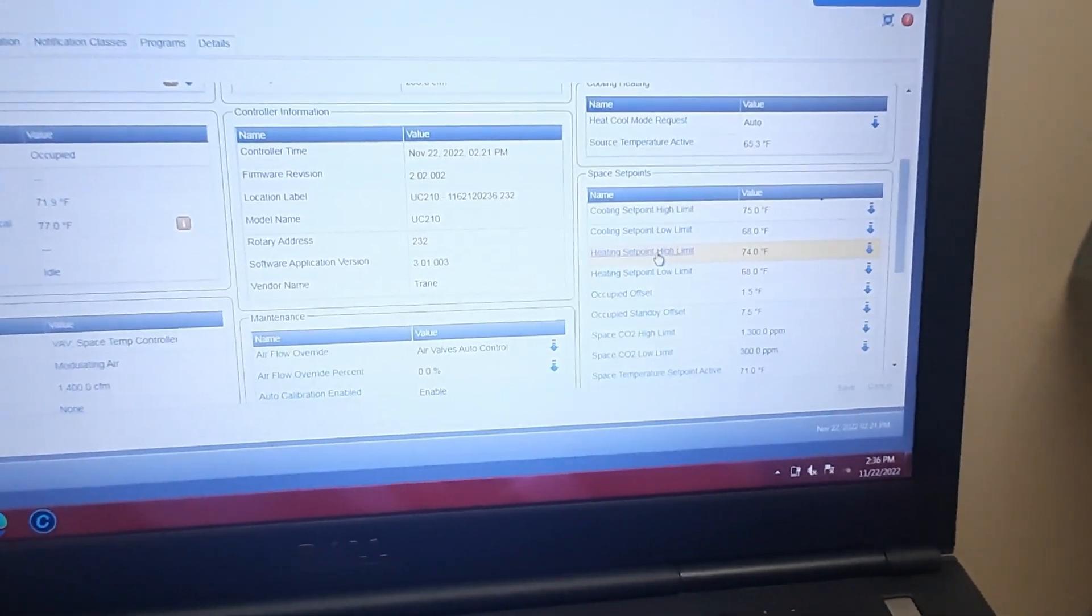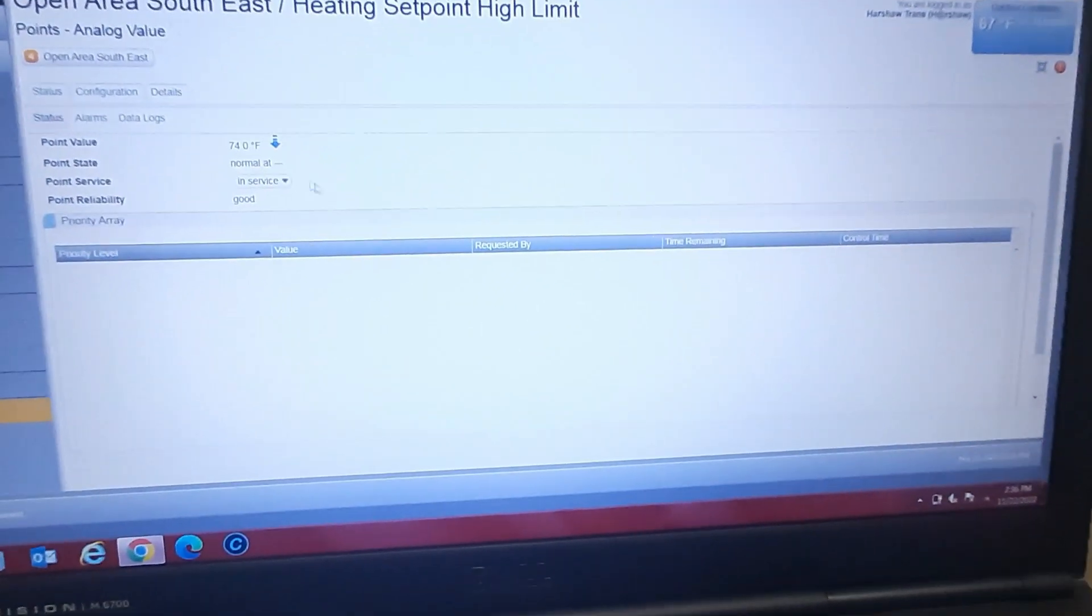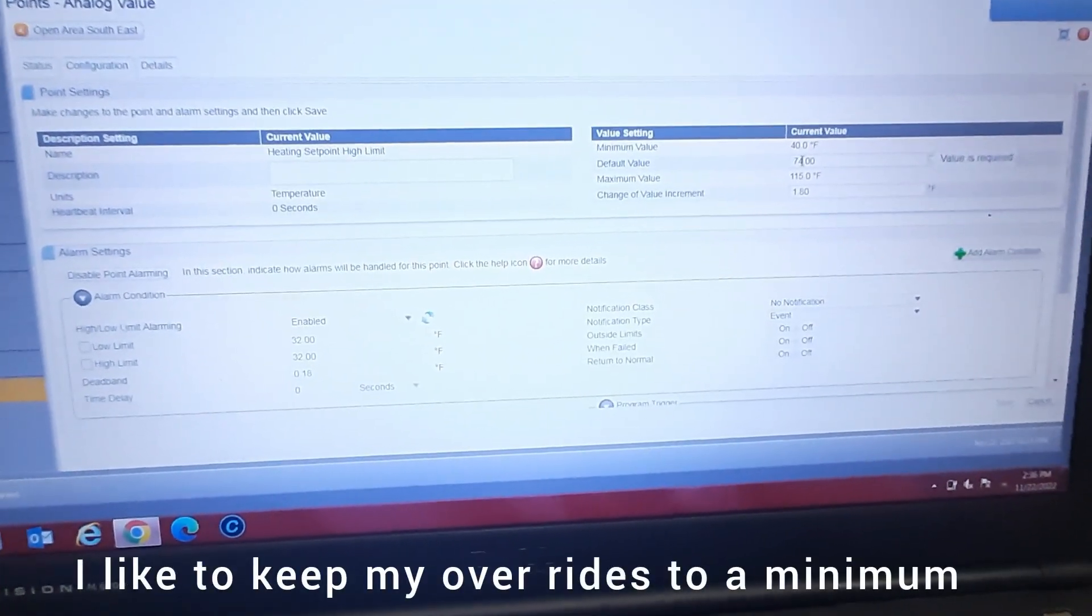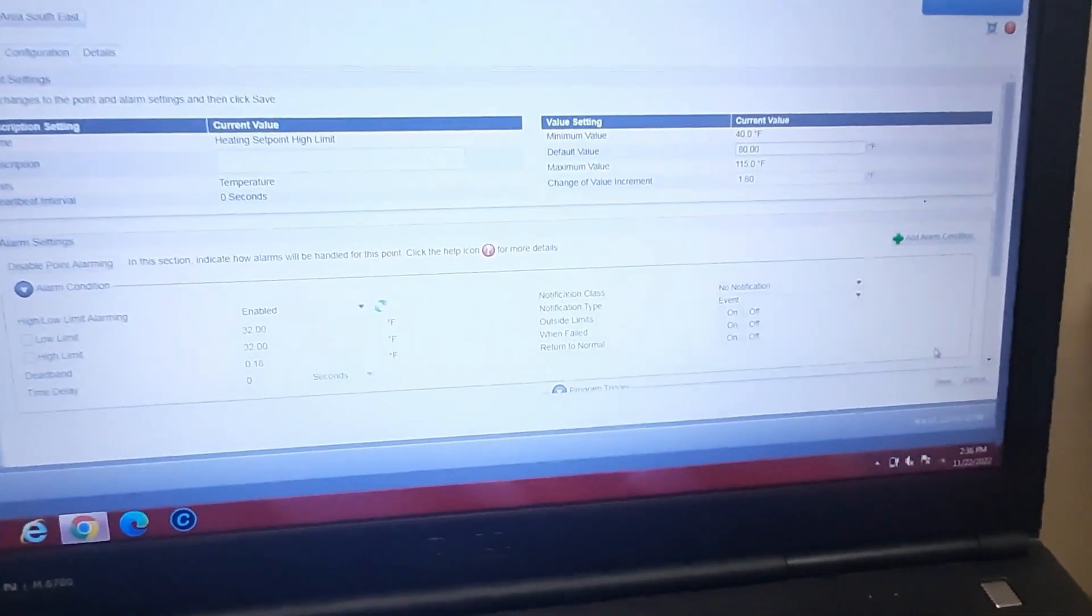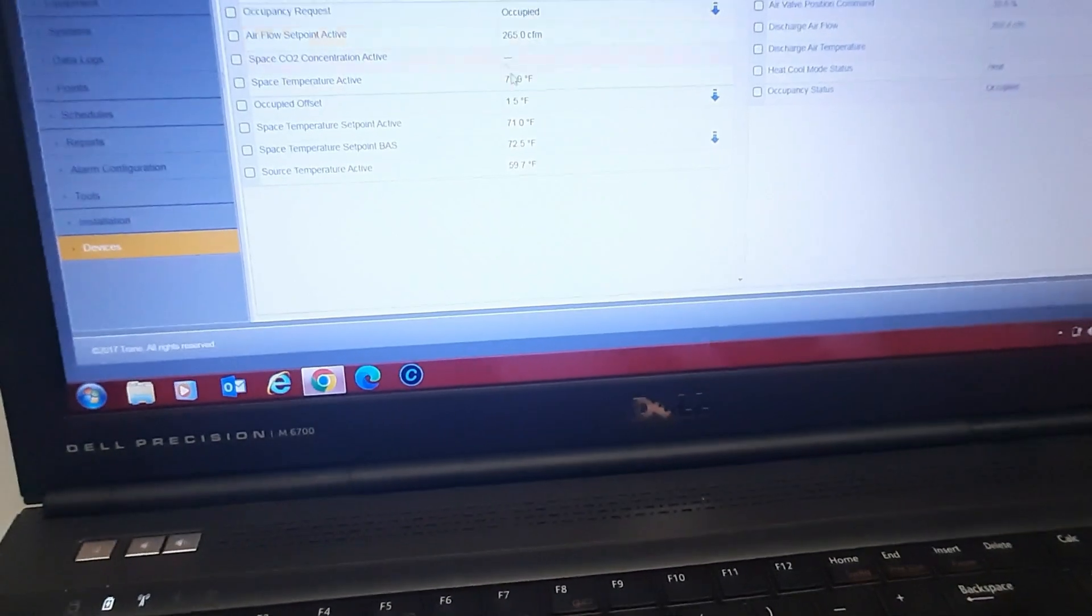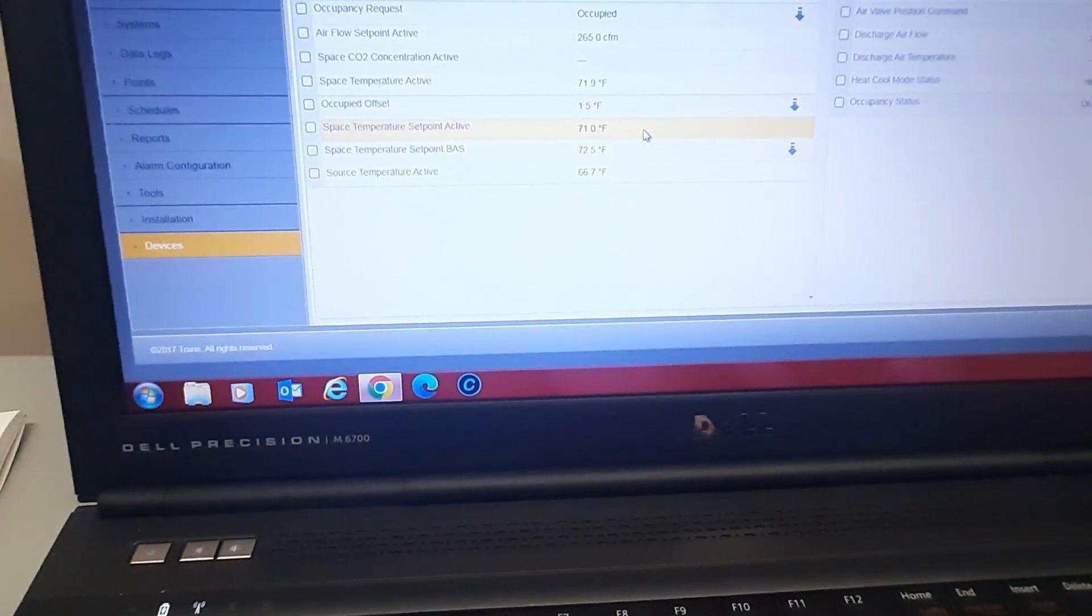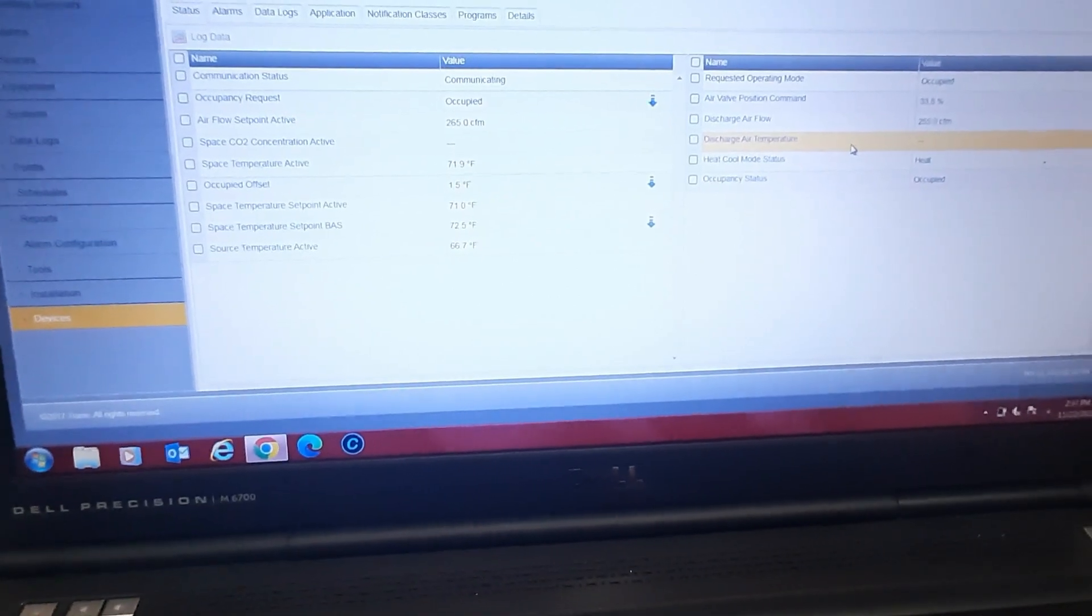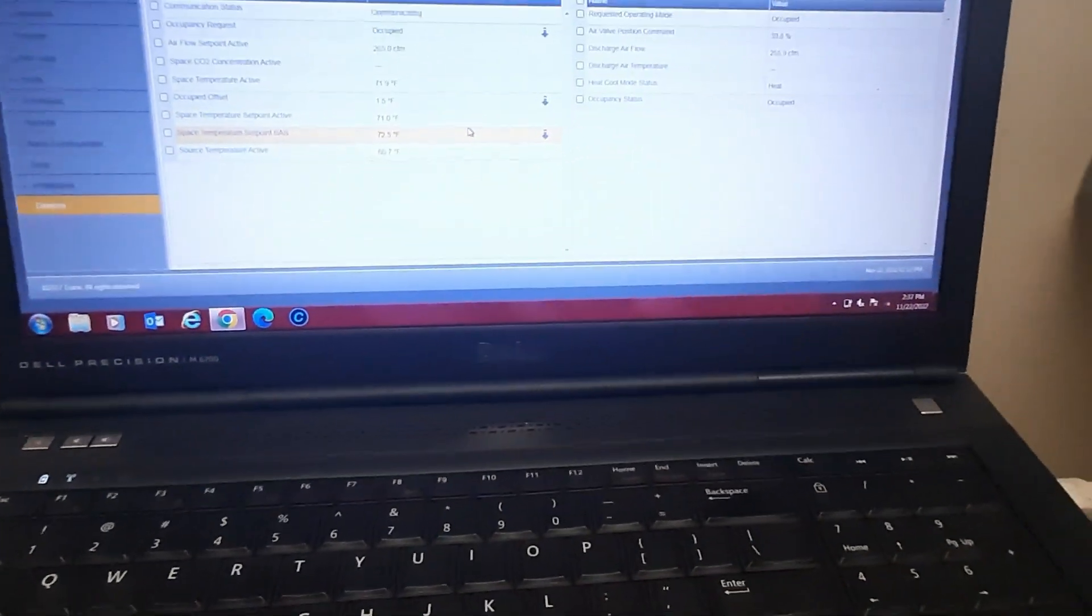Sorry if I'm a little shaky, it's hard to do this with one hand. I'm not sitting down either, I'm on one knee. So if you click on it you can change it by overriding it, you can click the arrow and just override it. But if you go to configuration you can actually change it for good. We set our cooling minimum down to 68 and then we'll give him, let's go maximum of 80. And then we'll go back and see, this should change now. The space temperature set point active, I'm going to go up and make sure it was set there and then we'll look at discharge air, that it doesn't have a sensor. We'll give this a few minutes and we'll have to go into the rooftop to check the warm-up set points.